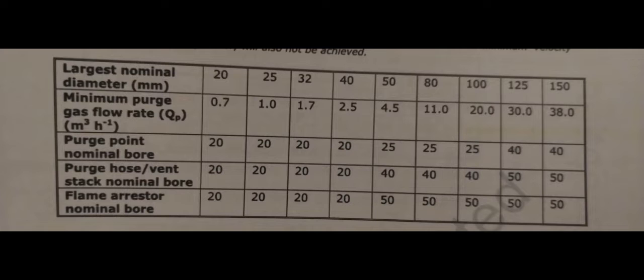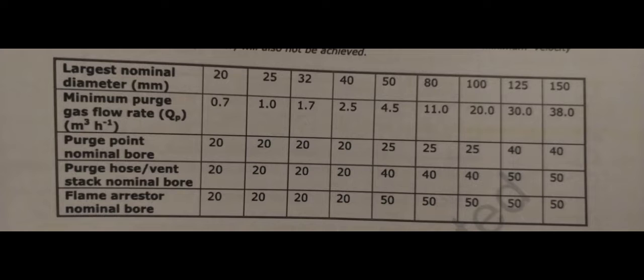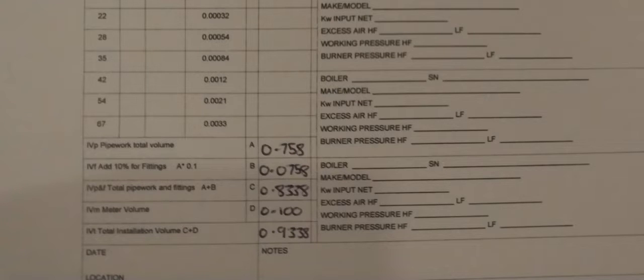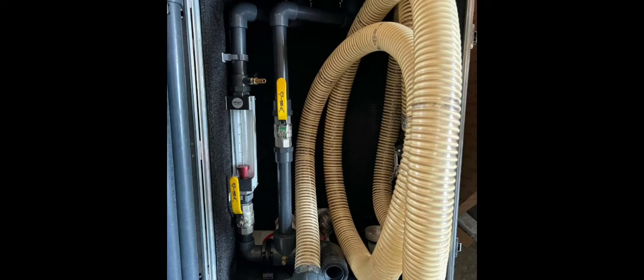Remember to also purge to the right time when you're purging from gas to air, not only air to gas. Make sure you've got the right flow rate, otherwise you can get stratification air pockets in your pipe. People are tending to use nitrogen more these days to purge because it's inert and a safer method. Here's the working out using my worksheet. In another video I showed you some purge equipment if you haven't seen it.